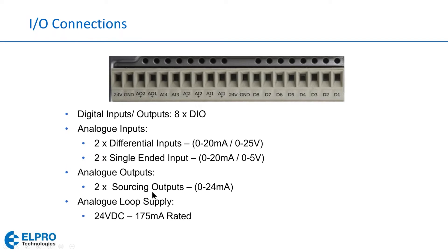There are two analog outputs that will drive power into the external device — they power the 4-to-20 milliamps. We also have an analog loop supply of 24 volts, so even if the radio's power supply is only 12 volts, internally the radio bumps that up to 24 volts, which is then available to power loop-powered instruments.